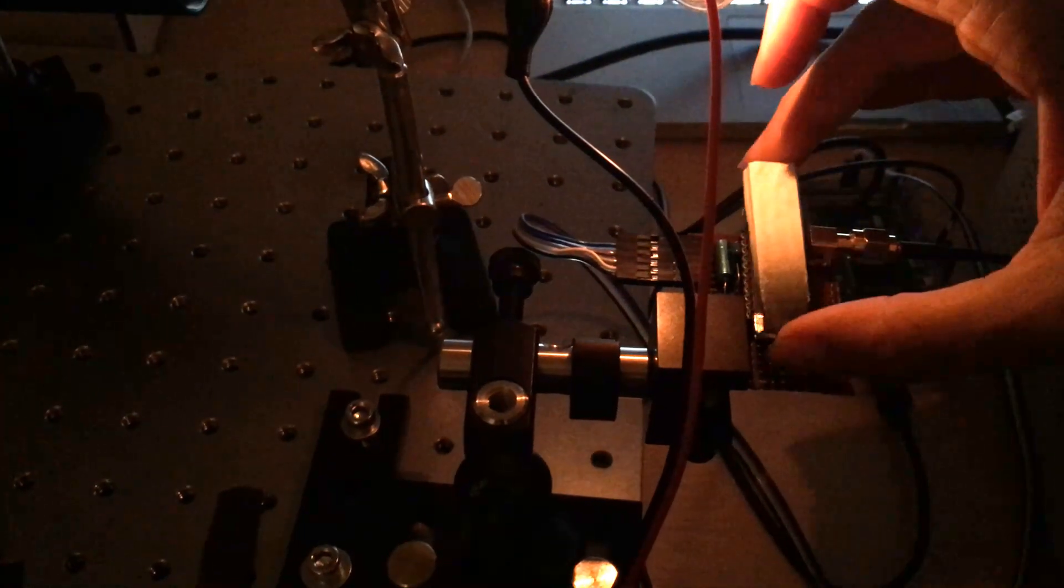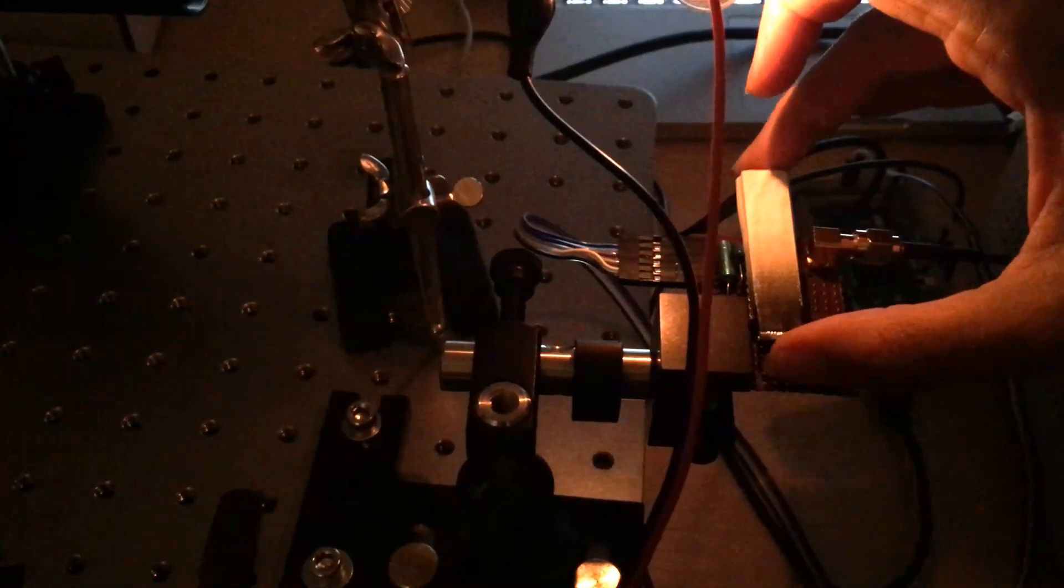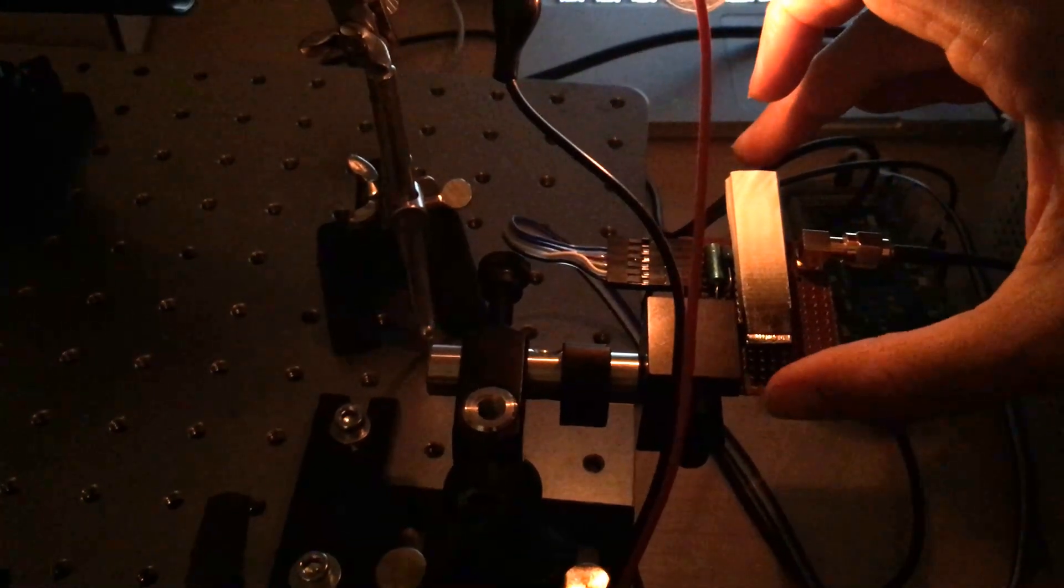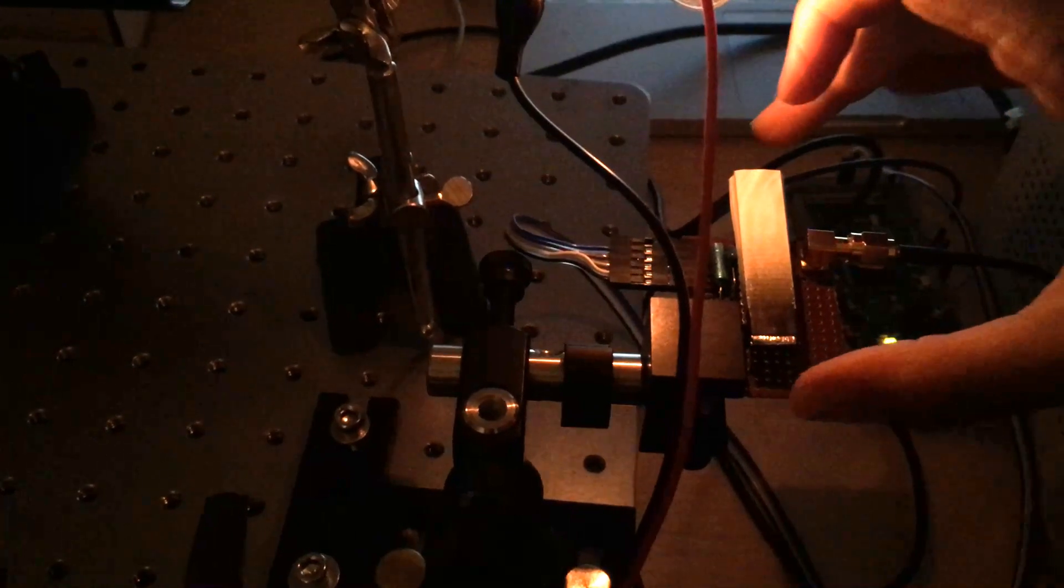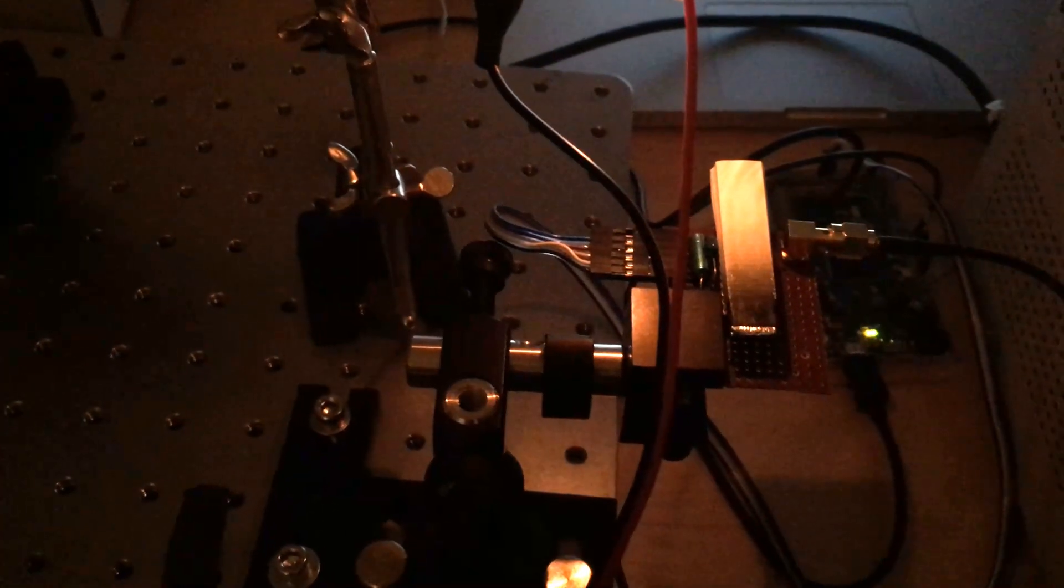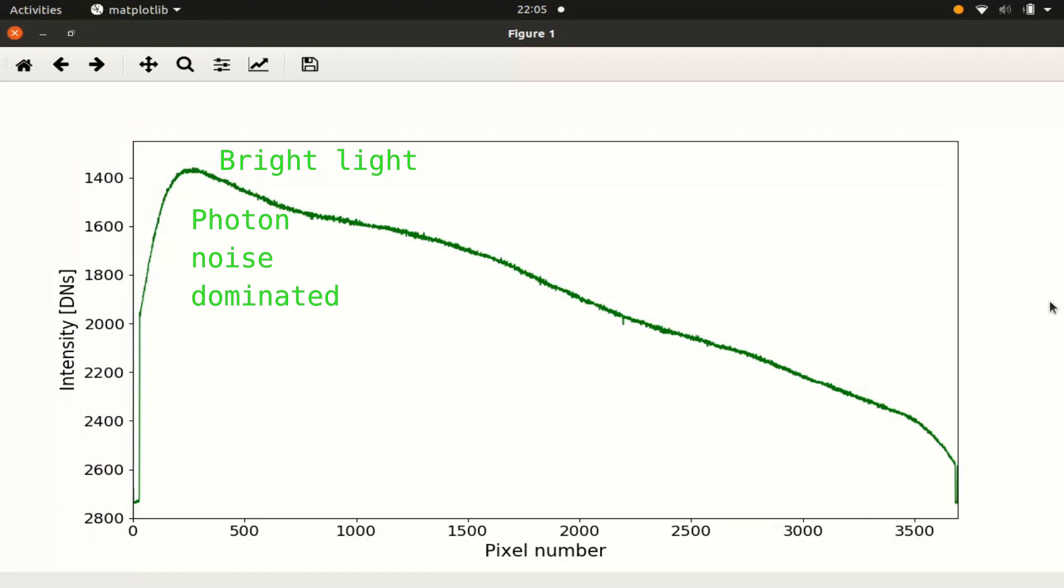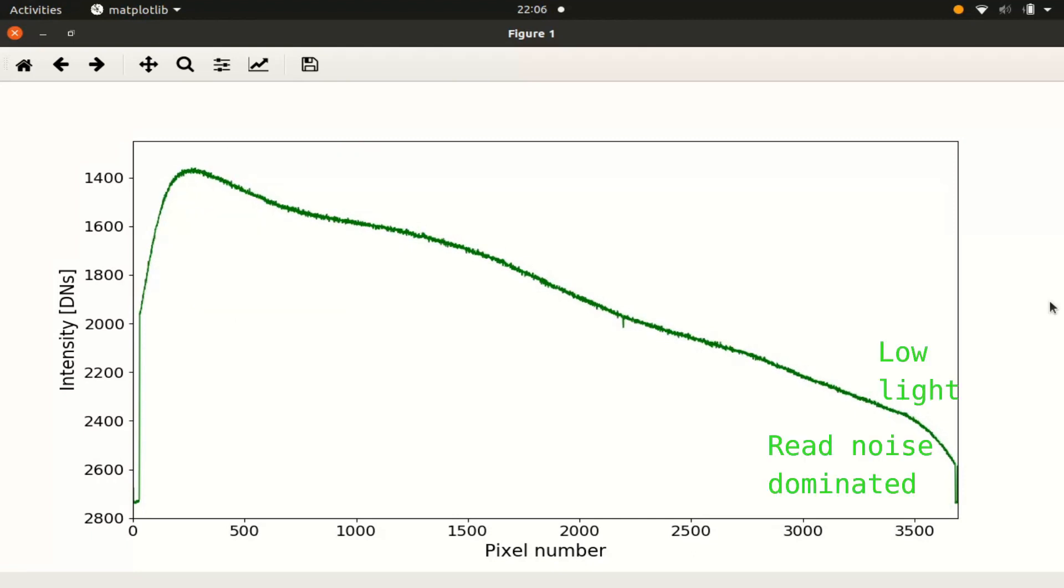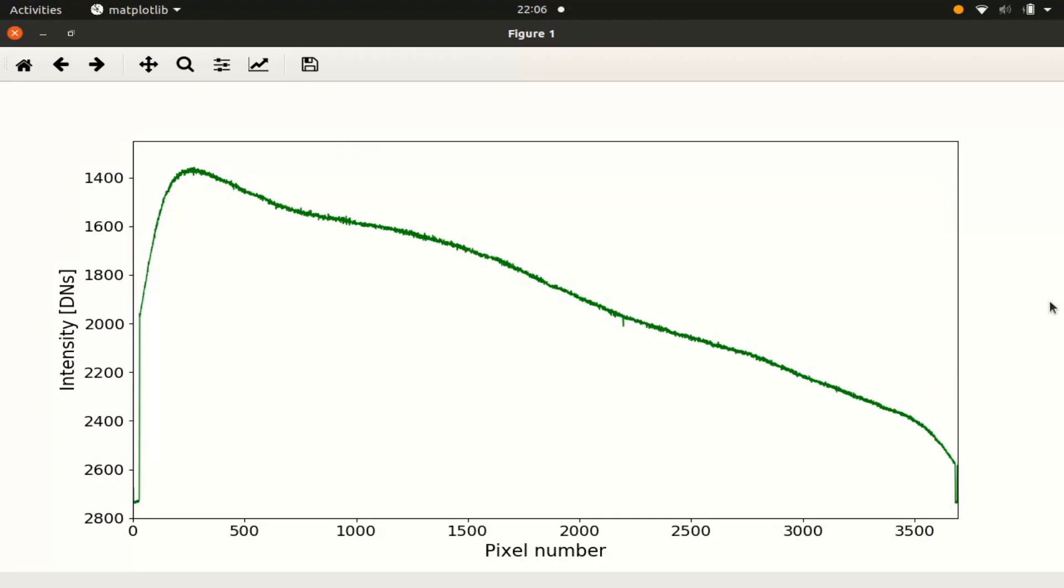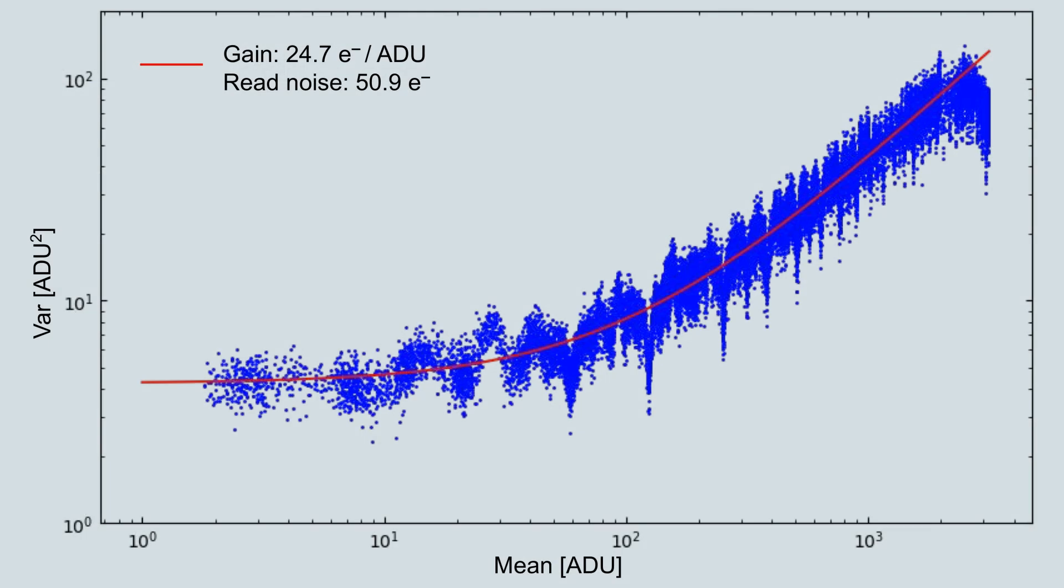To test the noise and linearity of the CCD, we made a grayscale target so that the pixels exhibited the full dynamic range from close to zero signal up to saturation. An ideal detector shows only Poisson noise associated with the detection of individual photons. Practical detectors have fixed additional noise, or read noise, which becomes dominant at low illumination. Thus, a CCD should show a linear relationship between the mean signal and the variance with an intercept equal to the read noise squared. We computed a pixel-by-pixel mean and variance for an ensemble of dark-subtracted scans. Here's the result. Each point represents an individual pixel. The red line is the best straight-line fit. The results show the CCD is linear up to approximately 2,000 ADU, and the read noise is 51 electrons RMS.